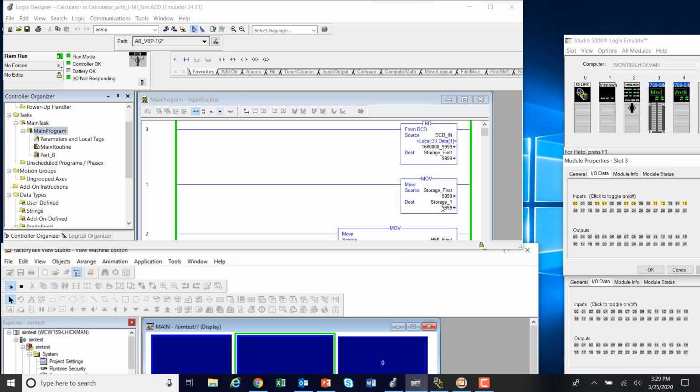So if you're having problems with sequencers, a sequencer array that you cannot manipulate the data on, or anything where we're working on the numbers, any kind of array, take it and move it into a tag, and then you can use that secondary tag to manipulate the data. You'll see what I'm talking about later on in the class. You'll be hitting your head that you can't do anything with this data. Do a move into a secondary tag, and then away you go.